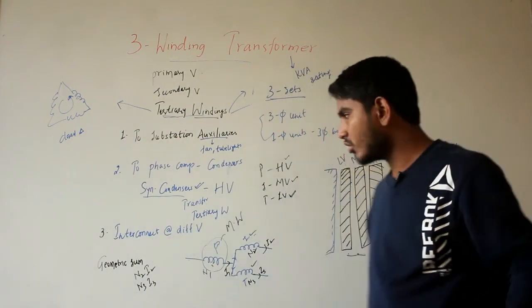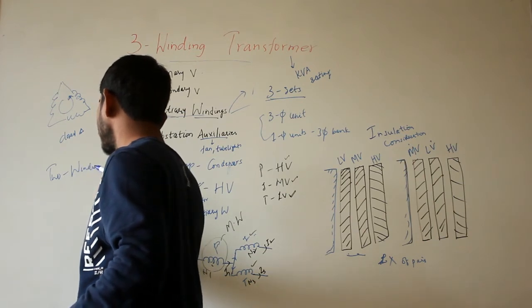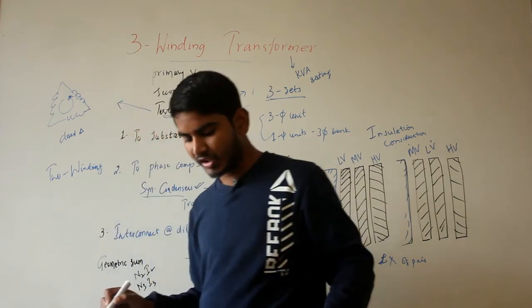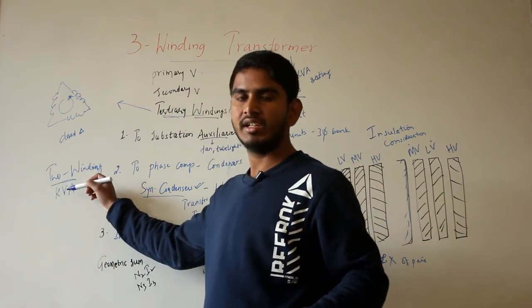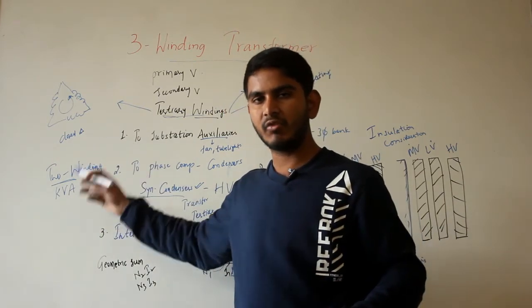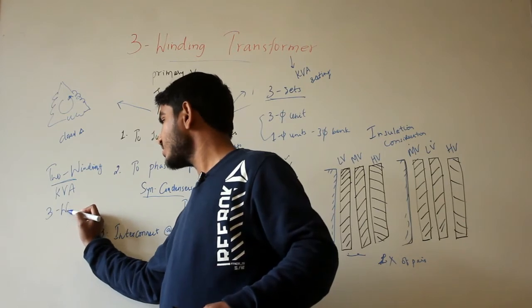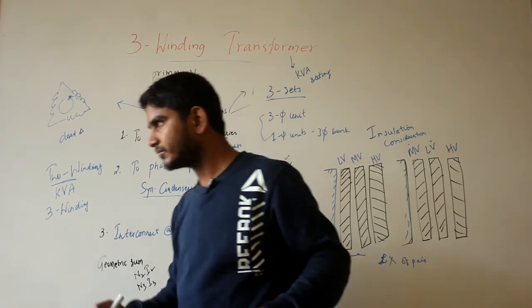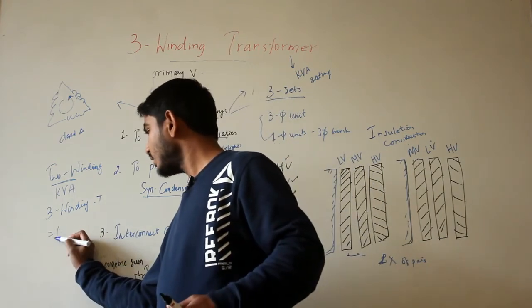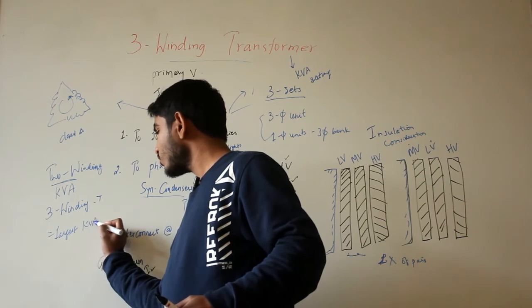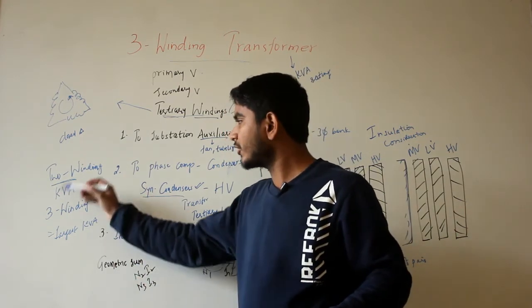Regarding ratings: in a two-winding transformer, the KVA ratings of the primary and secondary windings are the same, and that KVA rating is the rating of the transformer. But in a three-winding transformer, the three windings may have different KVA ratings, and the rating of the three-winding transformer will be equal to the largest KVA rating of any of the three windings. This is the most important difference compared to the two-winding transformer.